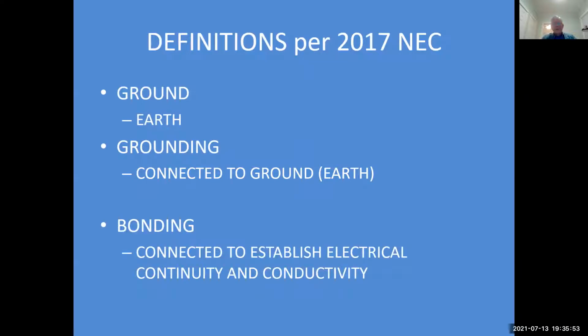Bonding, on the other hand, is when you connect two or more items to establish electrical continuity and conductivity. You can have equipment bonded together that's not grounded. You can have equipment that's grounded and not bonded. Ideally, you want both.